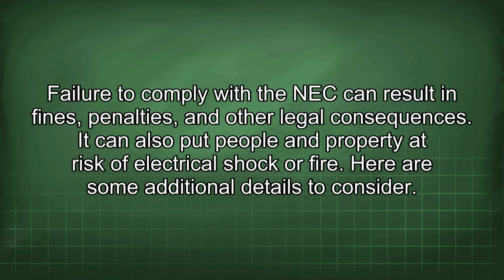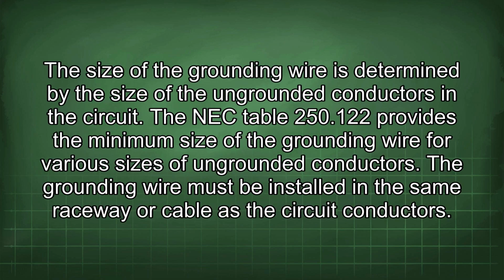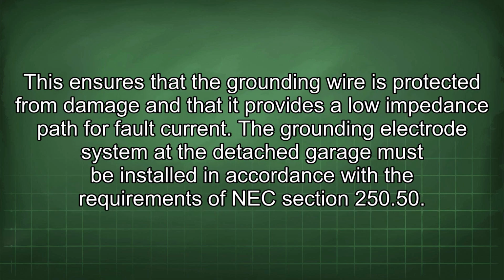Here are some additional details to consider. The size of the grounding wire is determined by the size of the ungrounded conductors in the circuit. NEC Table 250.122 provides the minimum size of the grounding wire for various sizes of ungrounded conductors. The grounding wire must be installed in the same raceway or cable as the circuit conductors. This ensures that the grounding wire is protected from damage and that it provides a low impedance path for fault current.